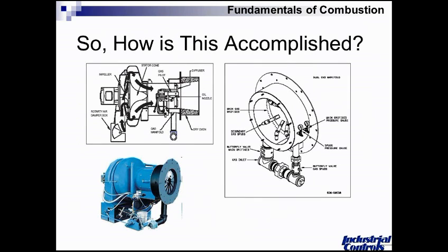This is a typical boiler burner made here in Wisconsin in Monroe. It's made by Industrial Combustion, but they all pretty much work very similarly. Here's a nice cutaway I found on the web. We've got an induction motor that's direct coupled to a fan. We draw combustion air from the surrounding environment. We add energy to it to build its static pressure, and the air passes from the left to the right through a diffuser where it mixes with fuel and then combusts out in this region called the oven. That's the root of the flame that's used to reflect heat back into the root of the flame to perpetuate ignition.